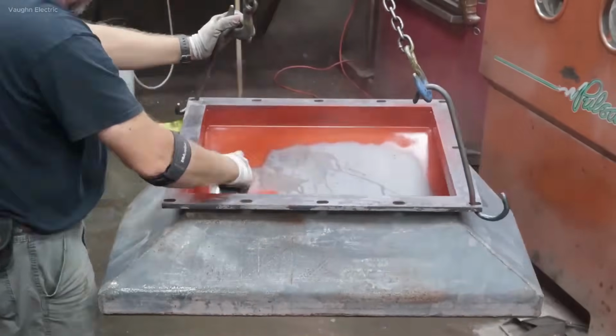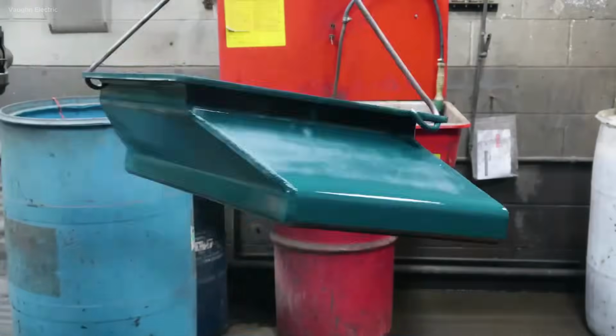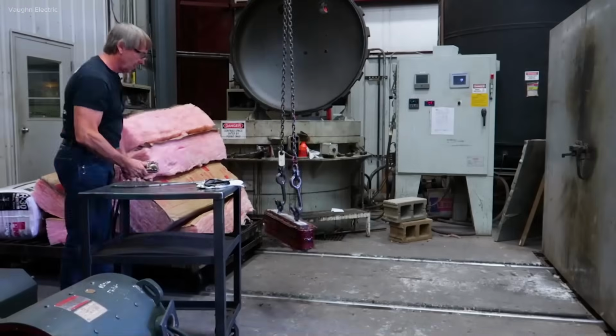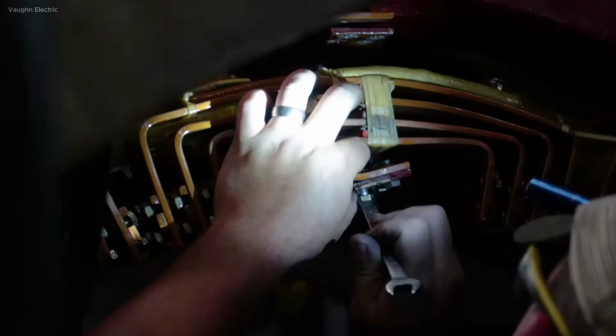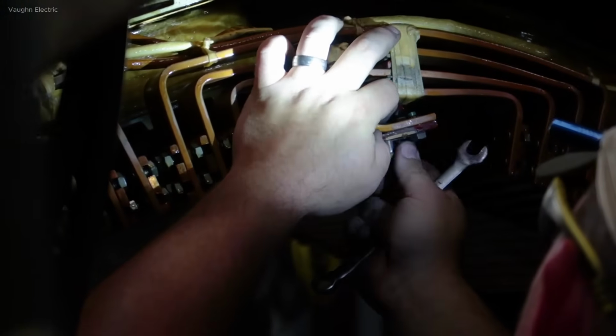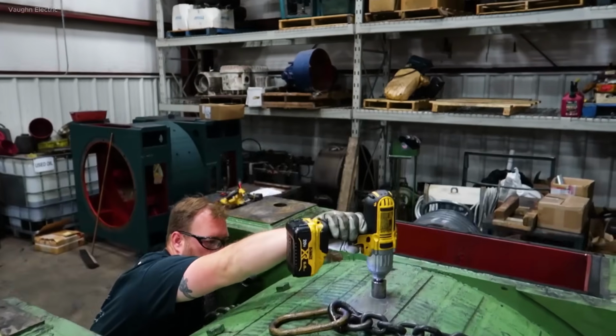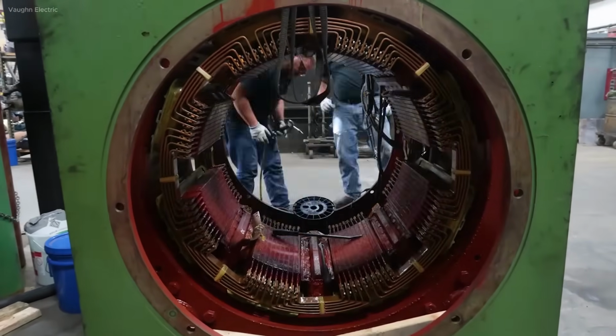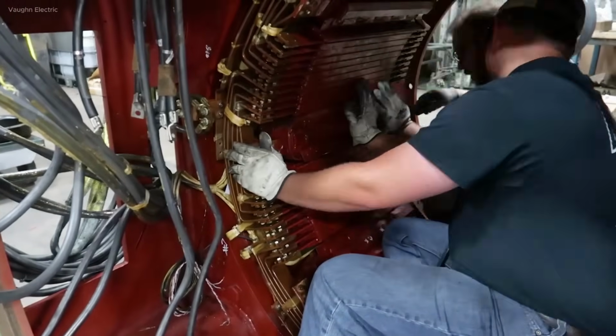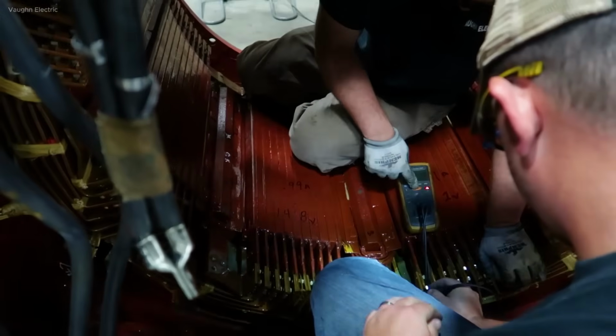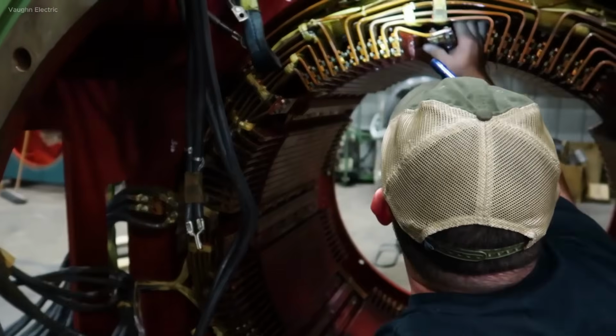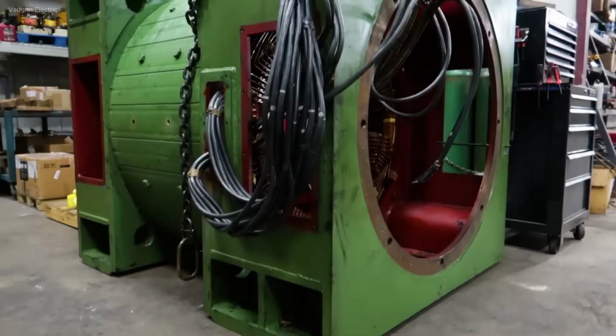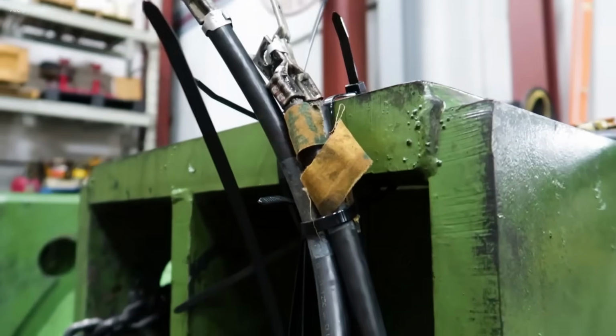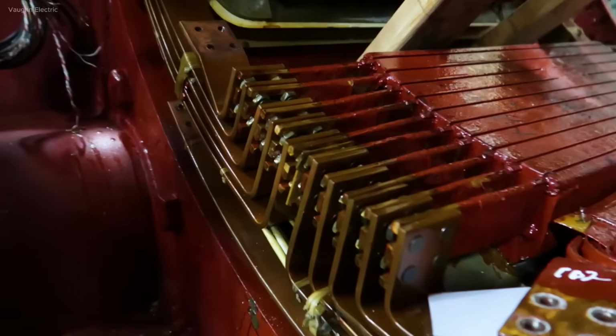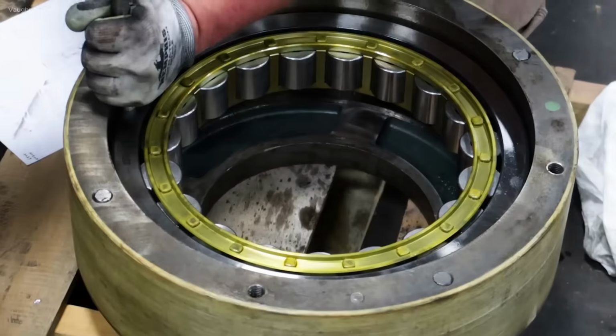While the stator cures, the rotor is inspected for bent shafts, cracked bars, or out-of-balance conditions. Rotors above 15 HP or 3,600 RPM are dynamically balanced using a 5,000 lb capacity machine. Balance corrections are made by drilling or adding weights. Shafts are polished or machined on a lathe to achieve a surface finish of 16 to 32 micro in and correct dimensions.